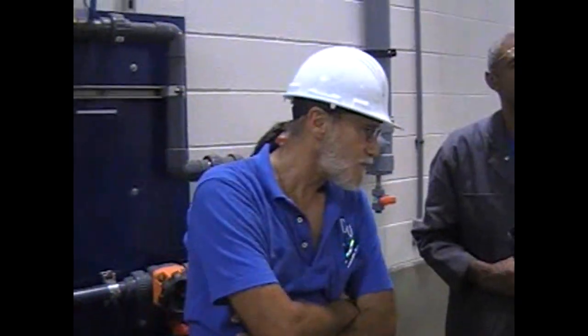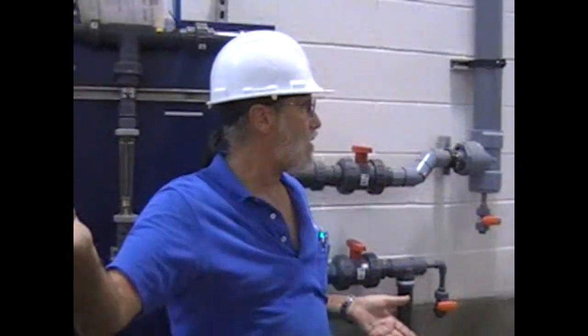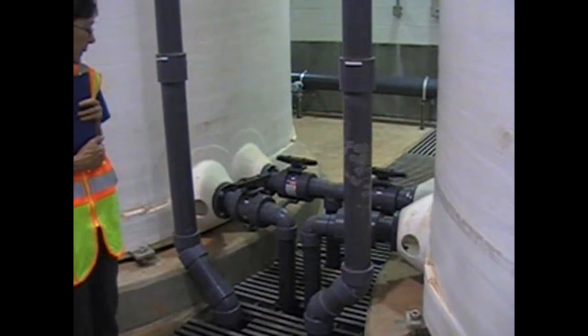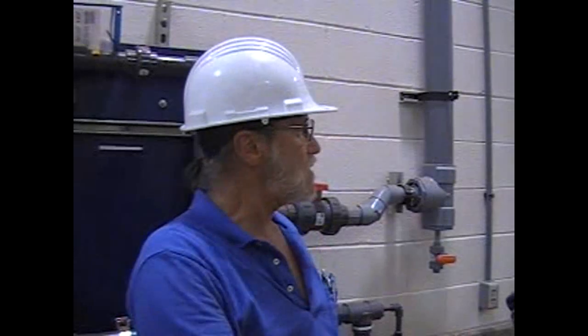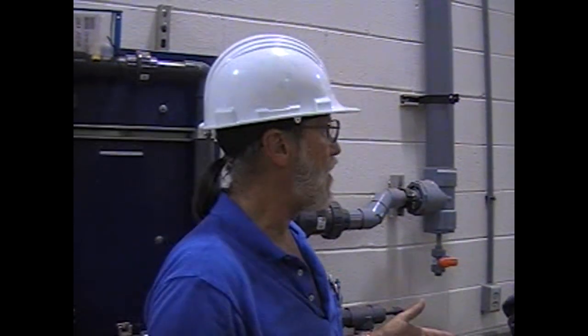Now, naturally, you're going to say, well, gee, I got all 8 in there. You want to put hot bleach on top? No. What you would do is use that series of interconnecting valves and feed valves there. You isolate. Let's just say, for argument's sake, by the time you figured out that you need a hot bleach backup, you had 40% in those tanks. What you would do, you isolate that tank, use this tank, and use it almost all up.